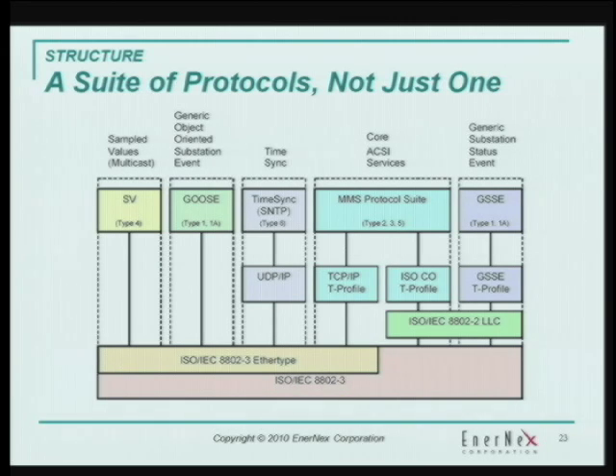The difference between a substation responding to a car hitting a pole and causing a short circuit, and making sure that transformer is simply de-energized rather than blowing up, can be a matter of milliseconds. So some things were done to support very fast connections.